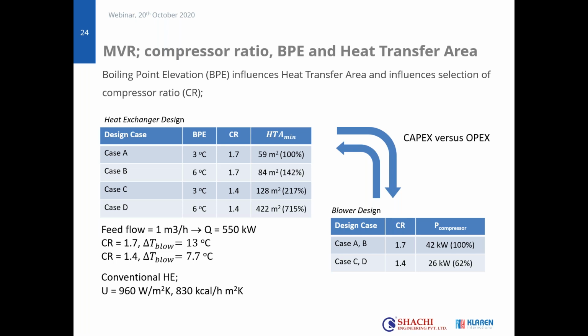So let's start with case A. In case A, I have a boiling point elevation of 3 degrees. I take a compressor ratio of 1.7. So that would mean that the temperature increase over the blower is around 13 degrees. So if you lower 13 with 3, you get 10 degrees driving force. It will be a bit lower because there is a temperature rise over the tube as well, but let's take roughly 10 degrees.